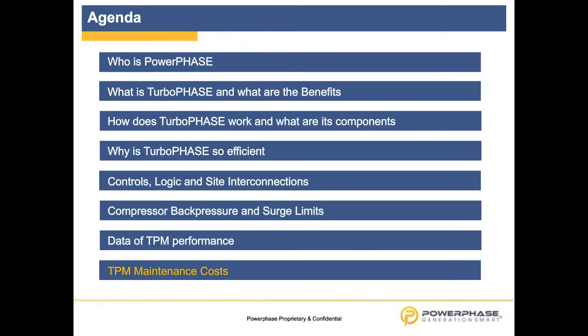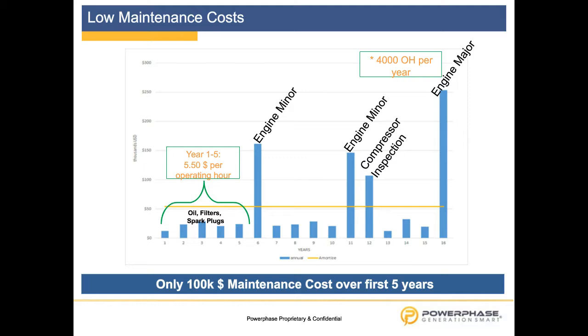I would now go into the TPM maintenance. I took this graph here. The basis is 4,000 operation hours per year, and on the lower axis you see the years. At 4,000 hours, for the first 5 years the maintenance cost would account for $100,000 US. The engine will have a minor after 24,000 hours, the second minor after 48,000 hours, and then the major at around 62,000 to 64,000 hours.